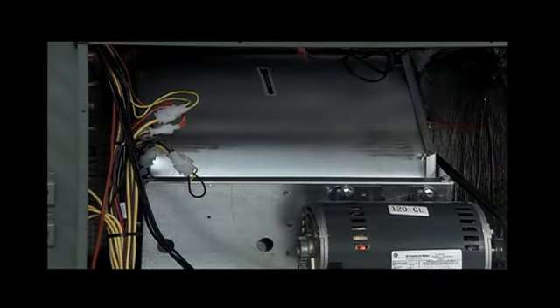The blower compartment is to the right of the gauge ports and can be accessed by quarter-turn fastener. To allow easy maintenance of the blower assembly, the entire assembly easily slides out by removing 3/8-inch screws from the blower retention bracket. The adjustable motor pulley can easily be adjusted by loosening the bolts on either side of the motor mount. Removing the bolts allows for easy removal of the blower pulley by pushing the blower assembly up to loosen the belt. Once the belt is removed, the motor sheave can be adjusted to the desired number of turns, ranging from 0 to 6 turns open.